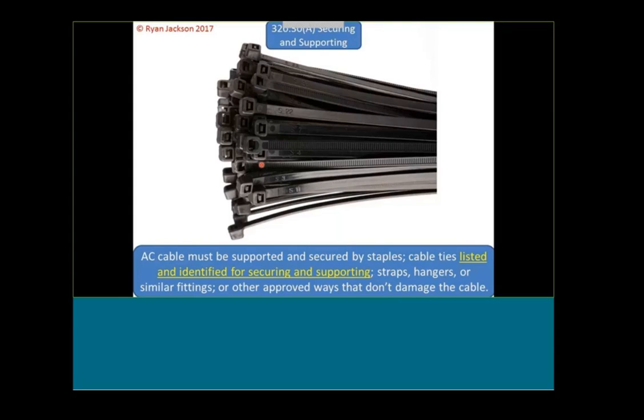So you've used these throughout the whole building, securing your MC cable to the ceiling grid and your cables inside the stud walls. The inspector comes by and says, hey, I want to see the bag those cable ties came in. You go out to the truck, show them the bag, and it's not listed. Well, you've got to go back through the whole building, first go buy cable ties that are listed, and then go back through and resupport, resecure all of your wiring.